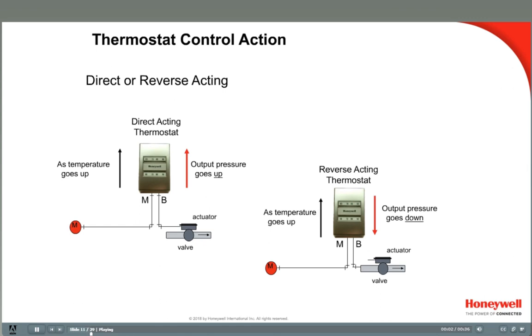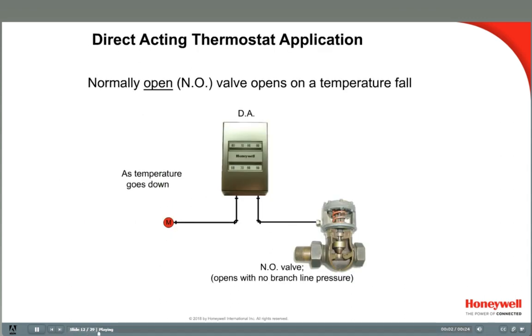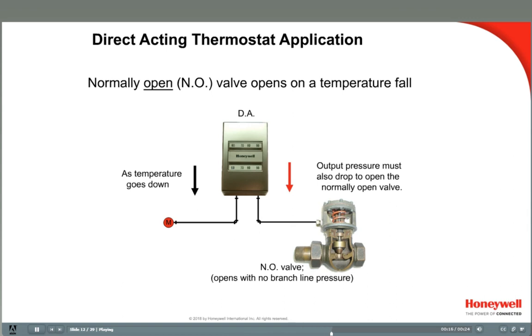Another option to consider when selecting a thermostat is whether it is direct acting or reverse acting. The direct acting thermostat has a direct temperature-to-output-pressure relationship — as the sensed temperature goes up, the outlet pressure goes up. The reverse acting controller has the opposite relationship — as the sensed temperature goes up, the output pressure goes down. For example, a fan coil unit with a normally open valve needs a direct acting thermostat, because as the temperature goes down, the valve must open to heat the room, and a normally open valve opens as air pressure to it falls.